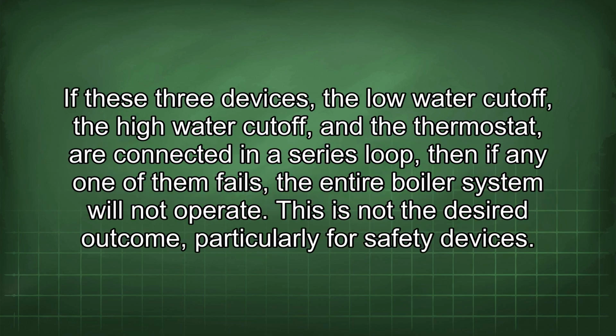If these three devices, the low water cutoff, the high water cutoff, and the thermostat, are connected in a series loop, then if any one of them fails, the entire boiler system will not operate. This is not the desired outcome, particularly for safety devices.